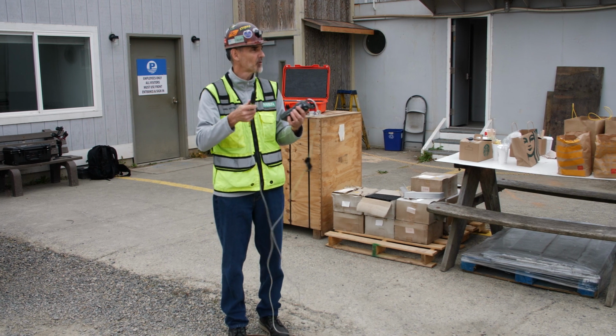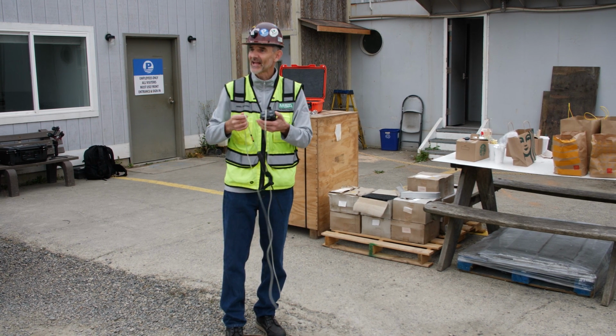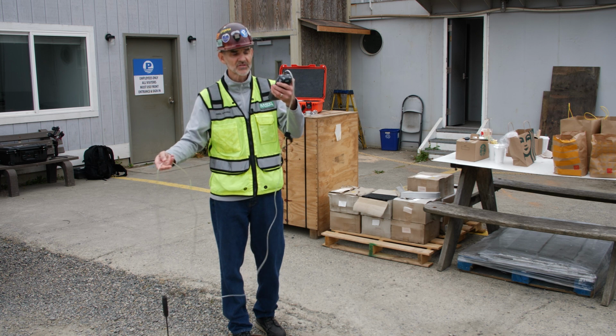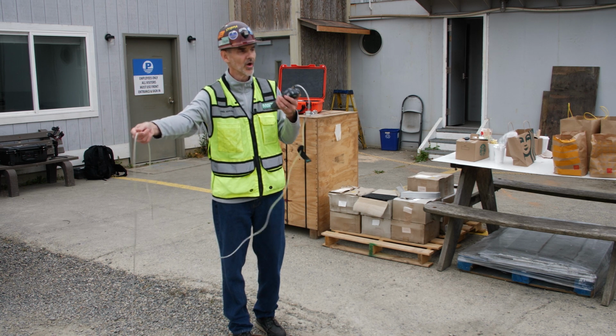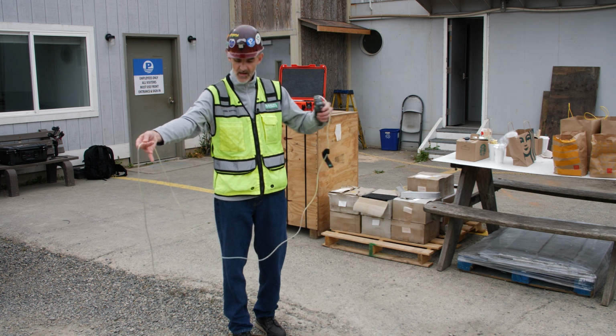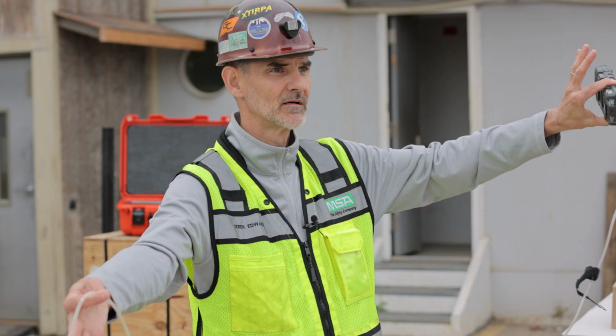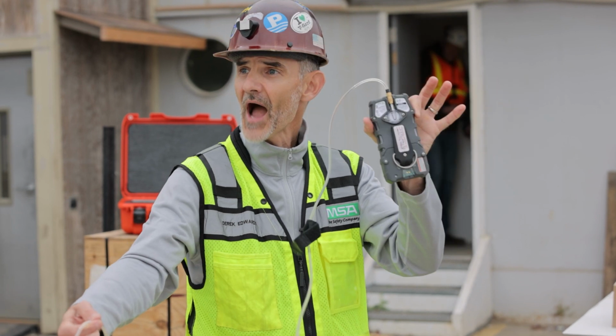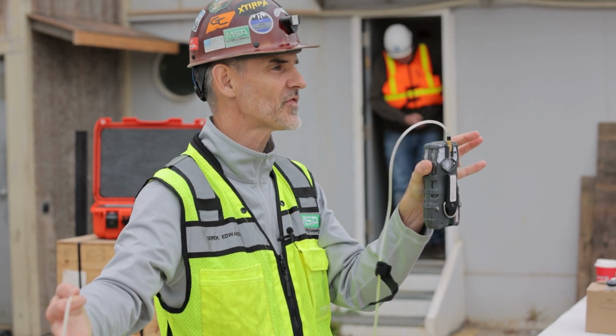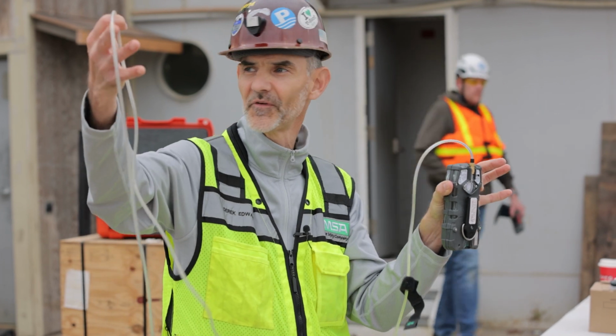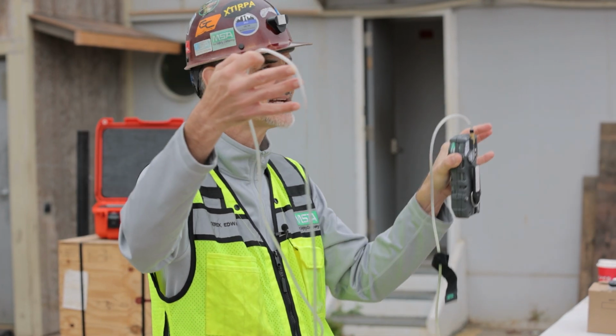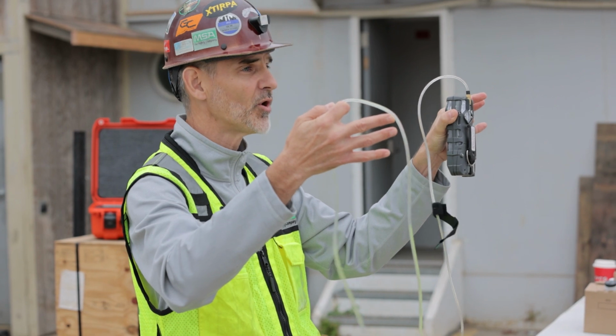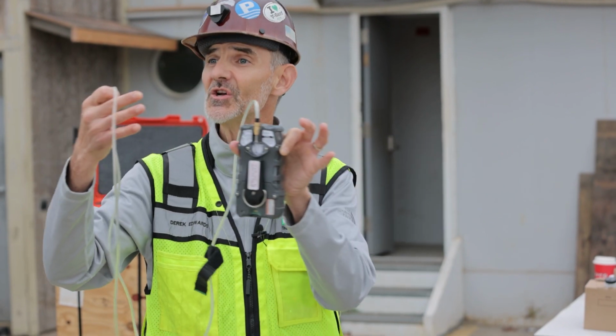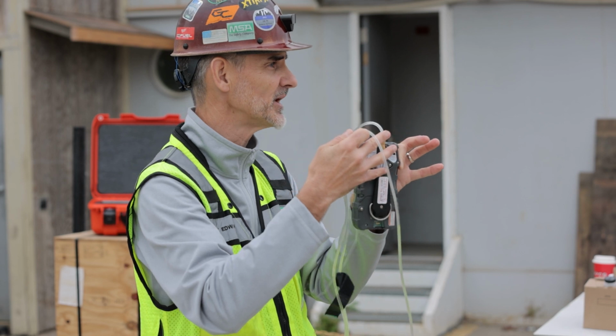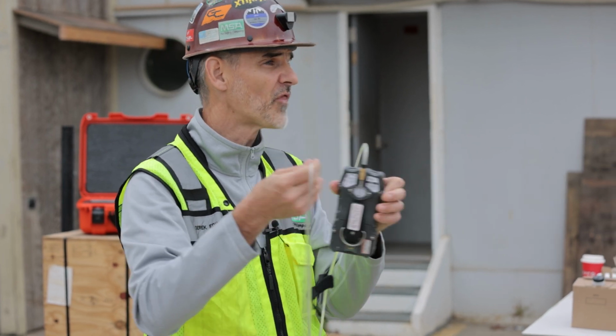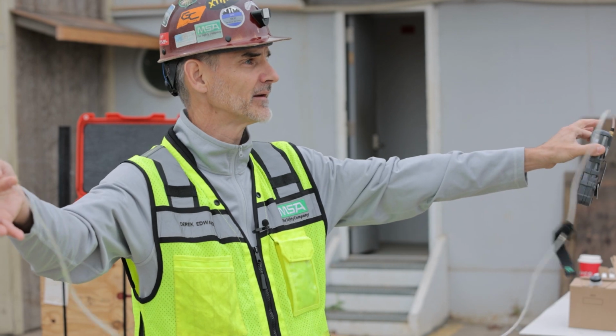During our confined space operation, first thing we're going to do is we're going to test that space. We're going to drop this down to the bottom of the hole, and we're going to pull a sample from the bottom, okay? There's 10 feet of sample line here. We're not going to be able to just drop this down, wait 3 seconds, and then pull it up 3 feet, wait a couple seconds. It does take time for this monitor to pull the air all the way through the tubing to the instrument for the sensors to read it, okay? So rule of thumb, 10 feet, 1 minute.